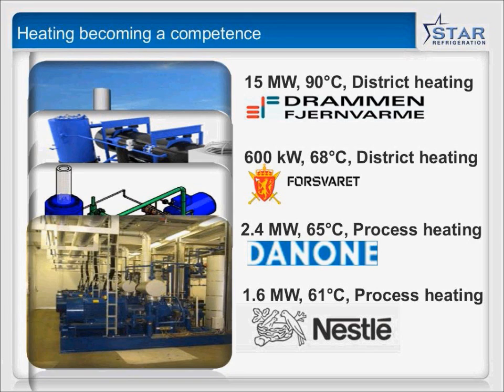Instead of having a £150,000 gas bill, you could use large heat pumps. I don't mean small domestic heat pumps, the efficiency on them isn't good enough, but these larger buildings need water circulating at 65, 70, maybe even 80 degrees.